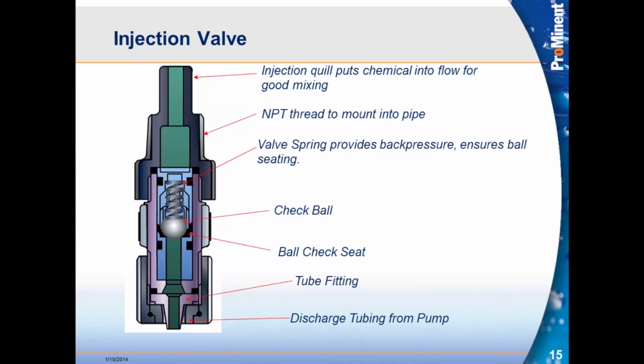So we have that quill or that nipple that sticks out into the flow, and we can cut that to length. So we want it to get out in as close to the center of the pipe, or at least as far away from the edge of the pipe as we can possibly do. Okay, this will prevent flow from coming back into the line between the pump and the injection point, or the back pressure valve in the injection point. We don't want to dilute that chemical because now we don't know what the concentration is. And if we're trying to dose versus off of volume and end up with a particular concentration, and we don't know what that starting concentration of our chemical is, we just can't control it. So this is a very important device for us.